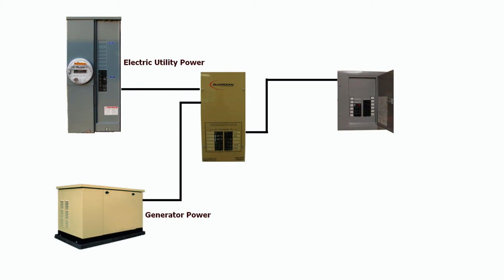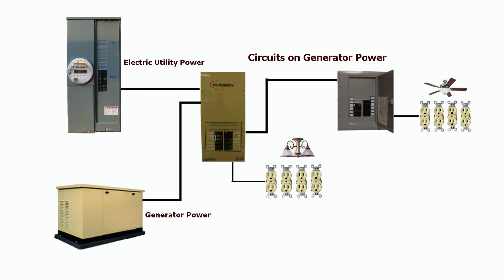In this case, this generator is about 16 kW, and so we're still limited to that size. Even though this transfer switch is 100 amp rated, and even the sub panel that's being fed off of this is a larger sub panel, we're still only going to get enough power that the generator is capable of putting out. But again, we're supplying the power from the electric utility company to the transfer switch panel. We've also got the generator power that comes into the transfer switch panel. When it's on utility power, the transfer switch power panel is on all the time, and so is the other sub panel that would be fed from it. But once the utility is gone, the generator fires up and it provides power out to the transfer switch and the other panel.